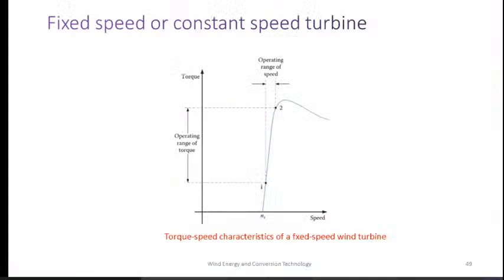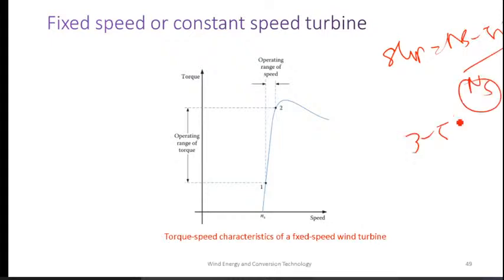So constant speed means it is always rotated at a constant speed. It means that it is not constant. That is the slip. The slip is equal to (ns minus n) divided by ns. The slip percentage will be 3 to 5%. So this 3 to 5% is the slip only.